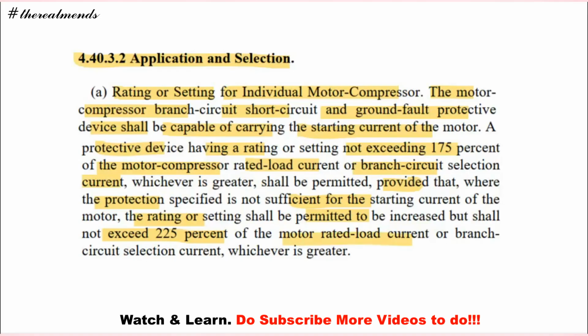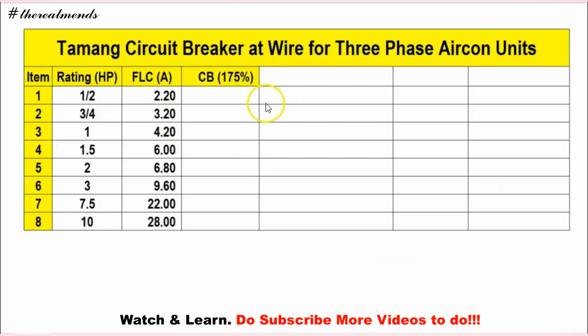So means to say, yung i-size up natin yung kanyang circuit breaker, so meron tayong factor na 175%, and then hindi lang siya lalagpas nitong 225%. So for the purpose of our calculations, prefer to use this 175% factor. Okay, so from the PEC code, so means to say itong ating FLC, i-times lang natin siya ng 1.75 to size up yung ating magiging circuit breaker.